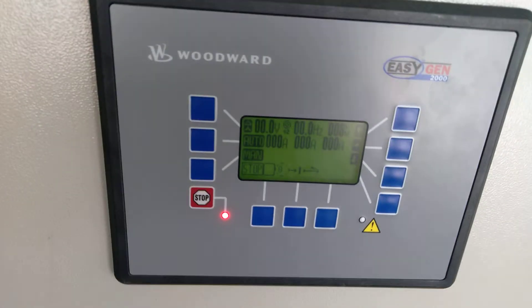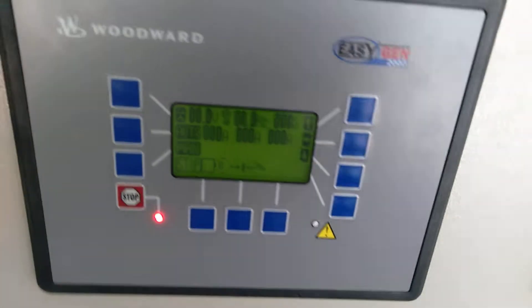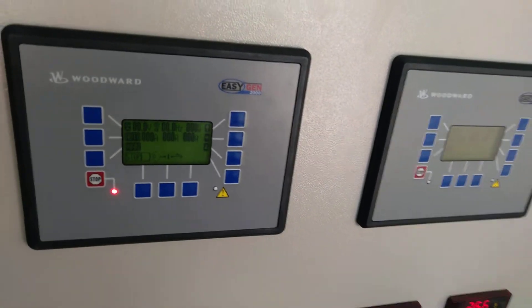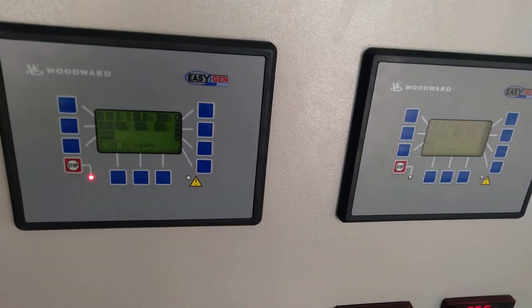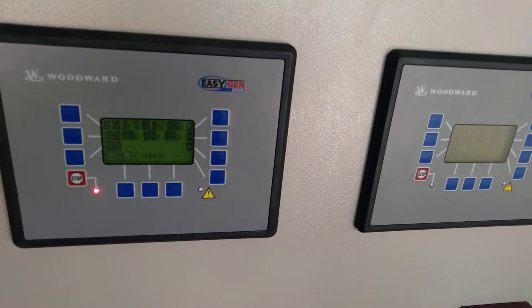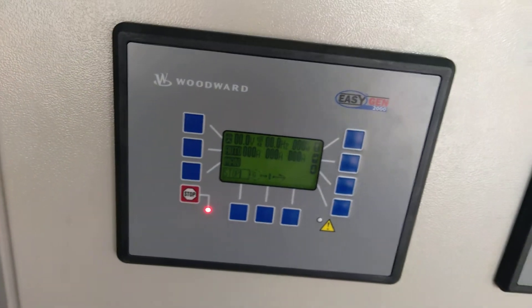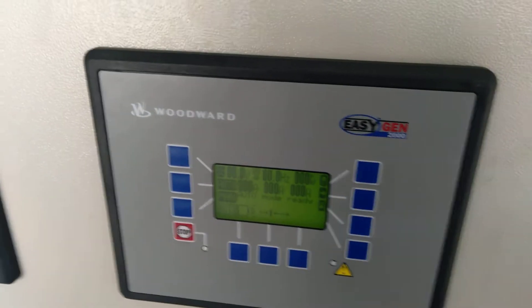Hello friends, welcome to our YouTube channel. We have another controller that we have repaired today. This is a Woodward controller — these were paralleled with one another and are installed for a 5kVA Cummins genset. One of them was bad; the analog output was not coming. We have successfully repaired it and now these are getting synced easily.